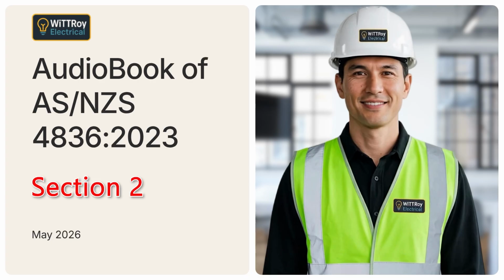Again, the key warning appears. All electrical conductors and parts, including neutral and earthing conductors, must be treated as energized until proven de-energized. Always test before touching. This is not just a sentence to remember, it is a work habit. Plan before touching. Isolate before touching. Test before touching. Prove before touching.